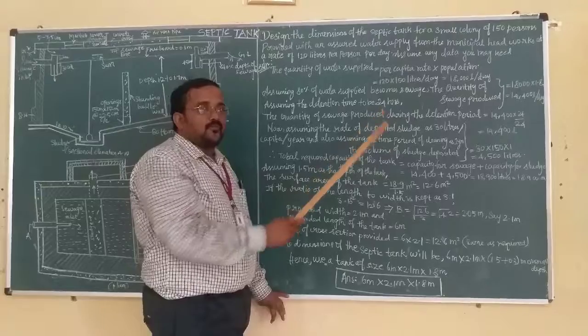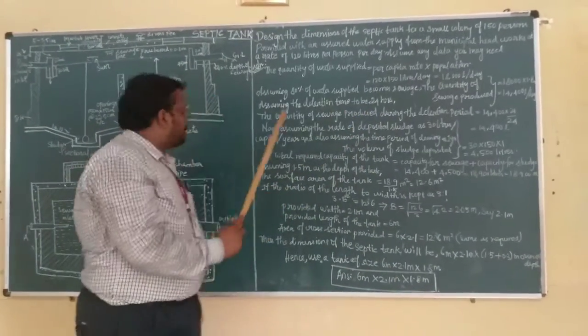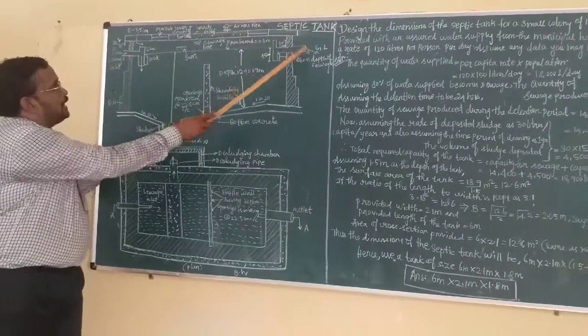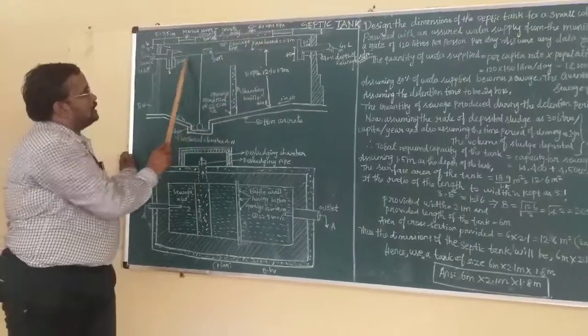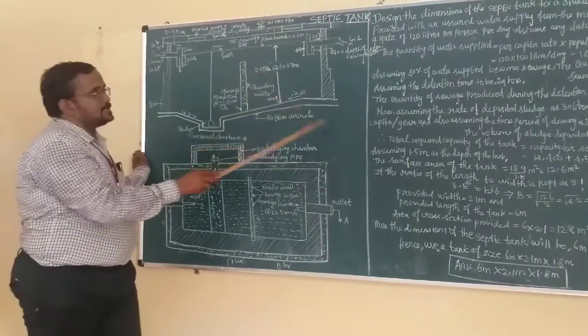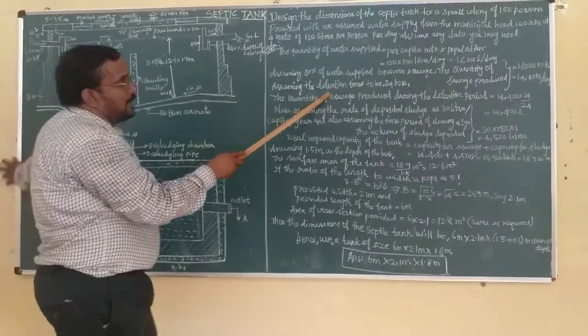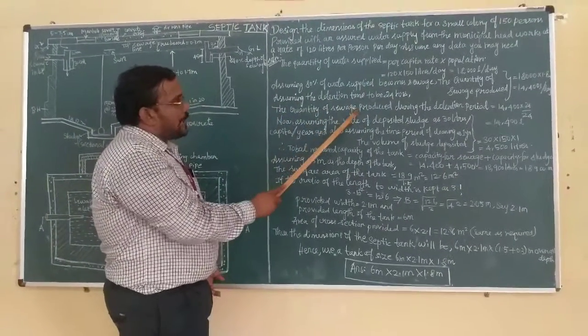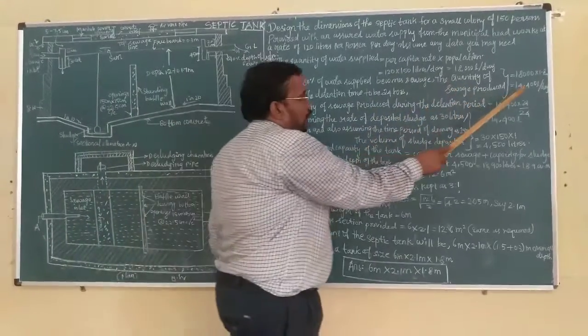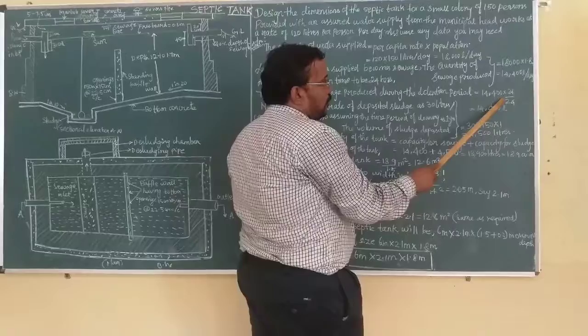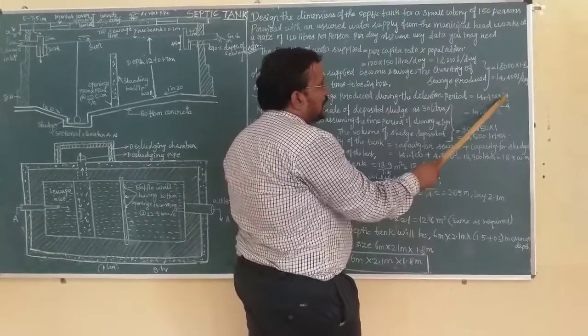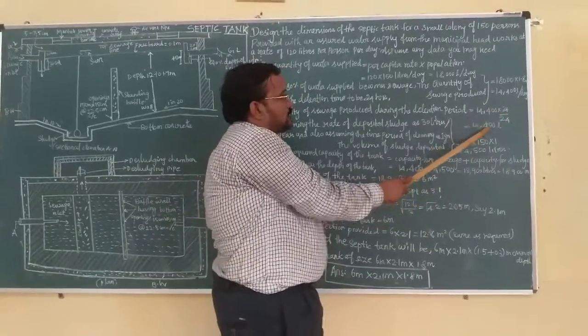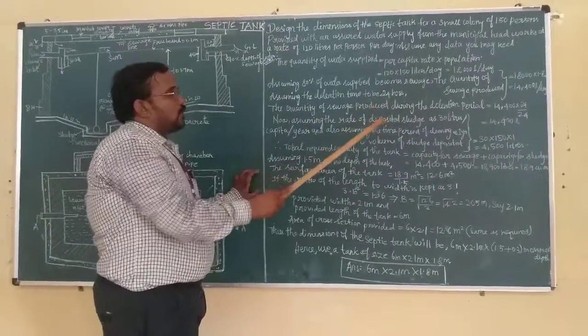Now you assume the retention time will be 24 hours. Retention time means what? Come to the diagram. See the inlet and the outlet. Time taken between the inlet and outlet - the time that sewage stays in the septic tank is the retention time. So retention time may be 24 hours. The quantity of sewage produced during the retention period: for one day, 14,400 liters per day. It stays for one day, hence 14,400 liters - that will be the quantity of sewage produced.